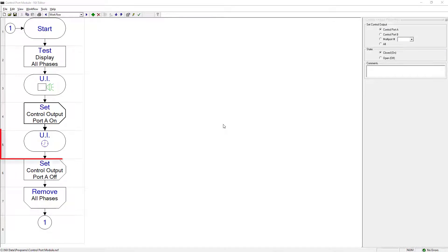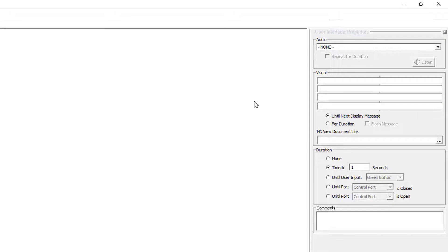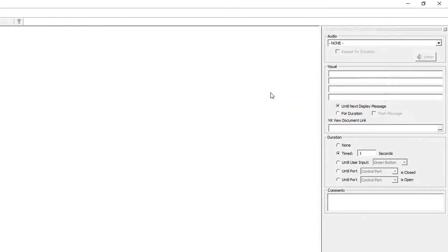The UI cell in step number 5 is used to set a delay of 1 second for this example program. This causes the control output to remain on for 1 second. Make any timing adjustments as the application requires in the timed field.